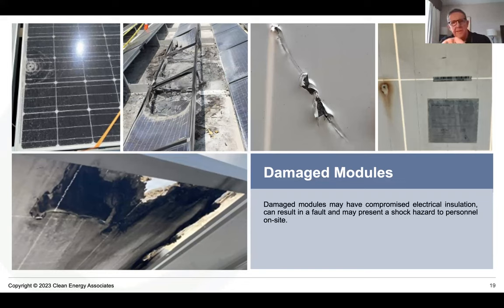So that picture on the left where that fire damage is on the top, that's from back sheet scratches. That was mishandling, and that could have been avoided by pulling those modules with the scratches and replacing them. And you wouldn't have had the downtime and the damage. I don't know, on this project, that damage right there was a good $40,000, $50,000 worth of fixing. So those are the things we want you to look at.